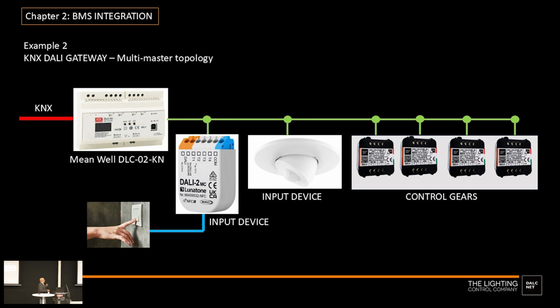Again, especially for big installations, what I sometimes suggest is to not rely only on KNX programmers, because KNX programmers know everything about KNX, and again, they don't know anything about how DALI works, how you should program it, how you should set the addresses, and so on. So maybe this speech is not so technical on this side, but these are more suggestions that we want to share, based on the day-by-day work that we are doing on the field.